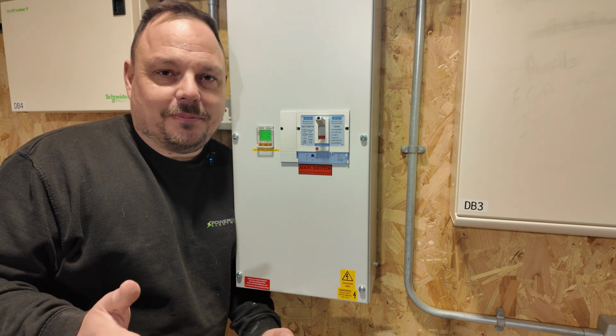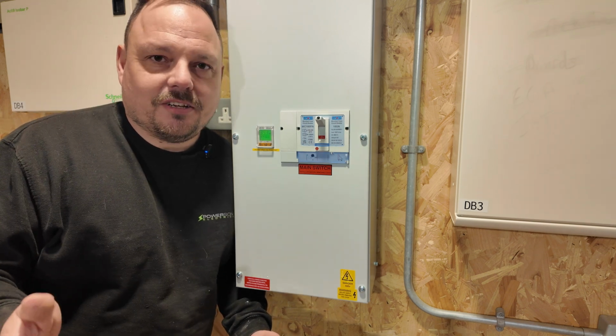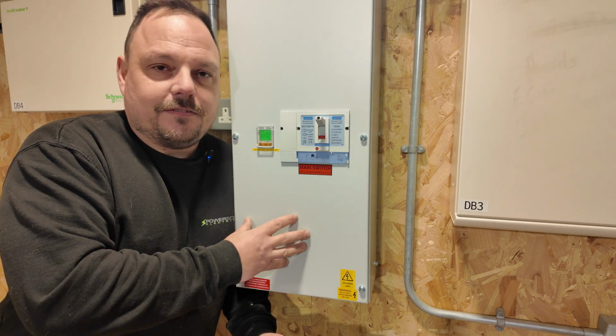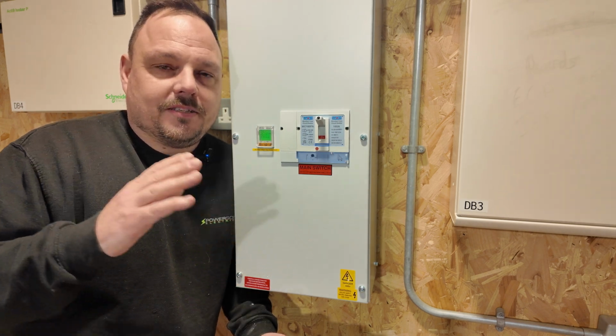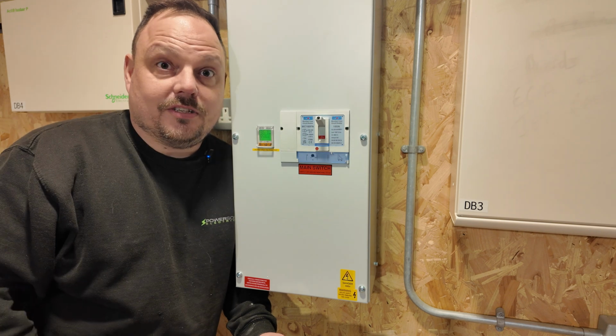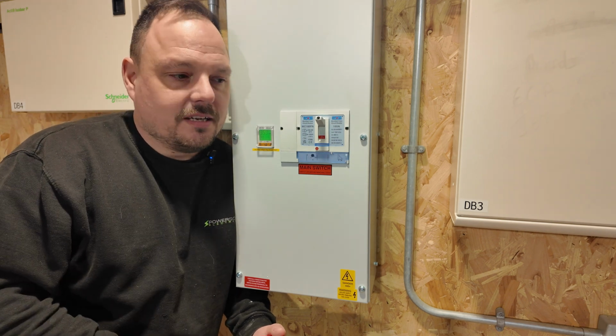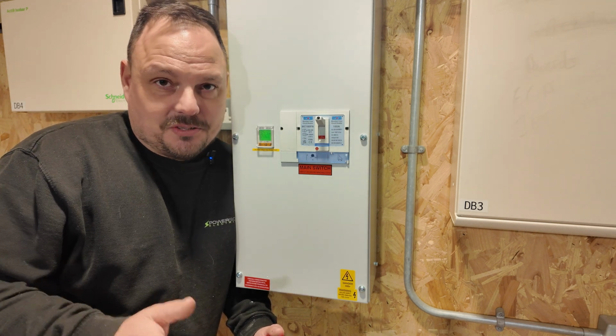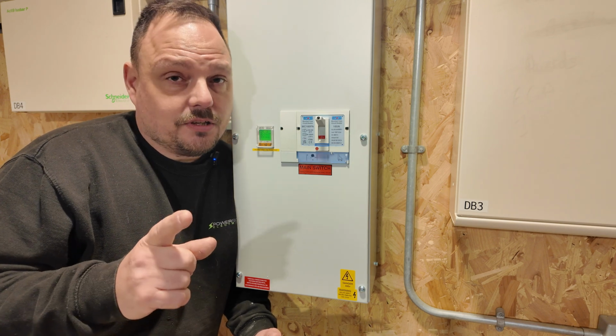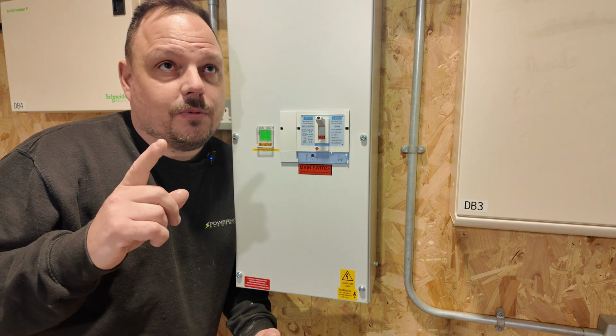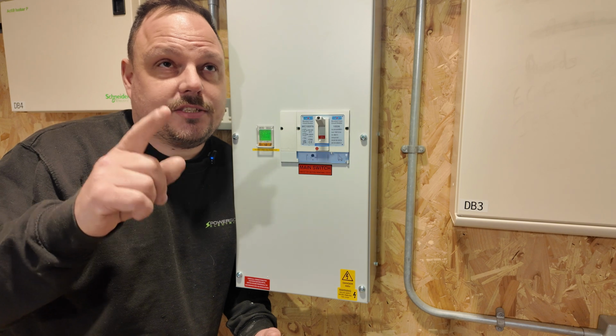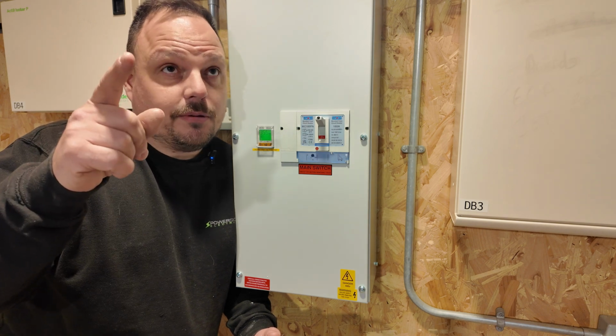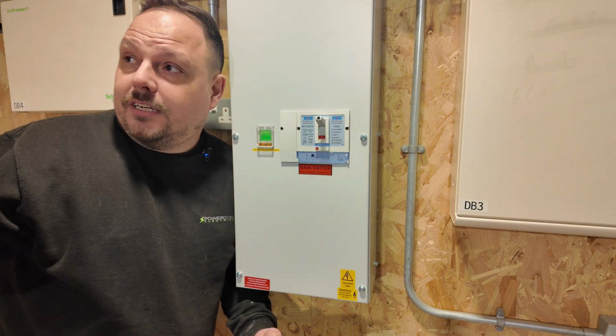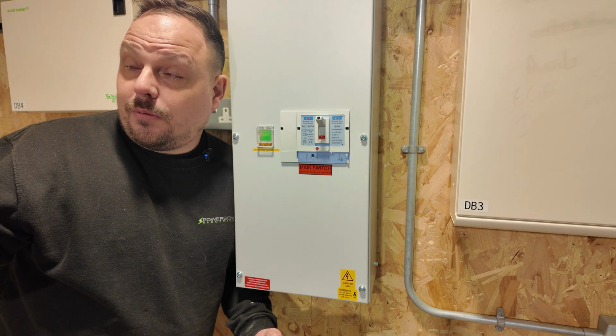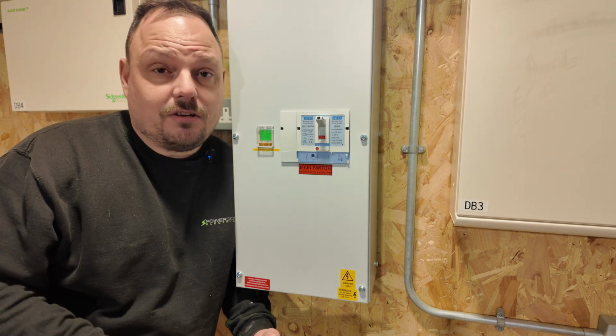That was by design, not how you'd do things in the real world. You wouldn't set it up like that on a proper customer's install, it's the last thing you'd want, a fault here impacting something on the other side of the warehouse. You just wouldn't want that, but I did want that for this, so we are where we are. It's an interesting test for another day, we can take out the other RCDs. That one over there won't be a problem because it's steel wire armour leading over, and that one won't be a problem either, also steel wire armour. So yeah, they can all come out.